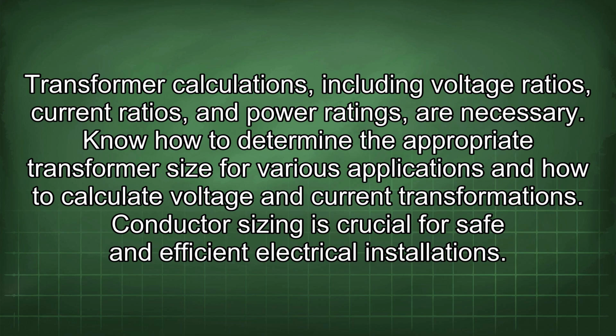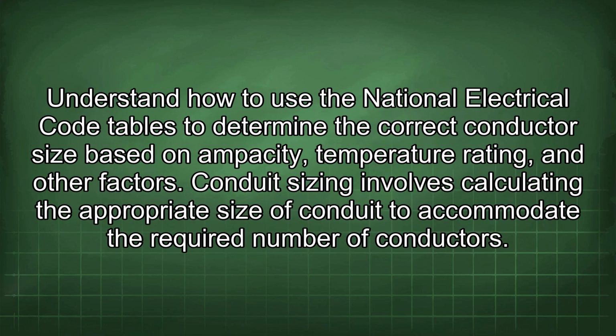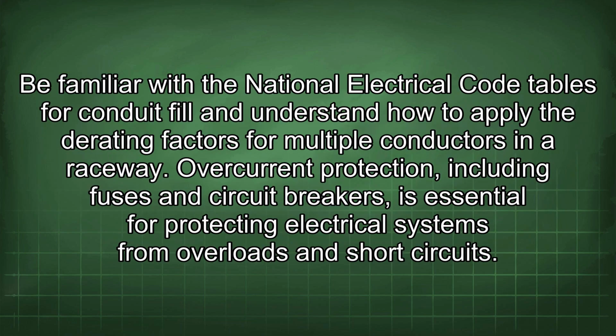Conductor sizing is crucial for safe and efficient electrical installations. Understand how to use the National Electrical Code tables to determine the correct conductor size based on ampacity, temperature rating, and other factors. Conduit sizing involves calculating the appropriate size of conduit to accommodate the required number of conductors. Be familiar with the National Electrical Code tables for conduit fill and understand how to apply the derating factors for multiple conductors in a raceway.